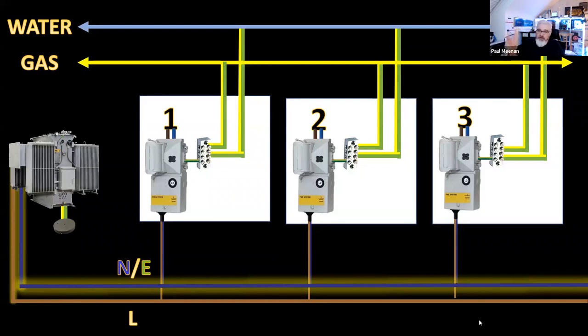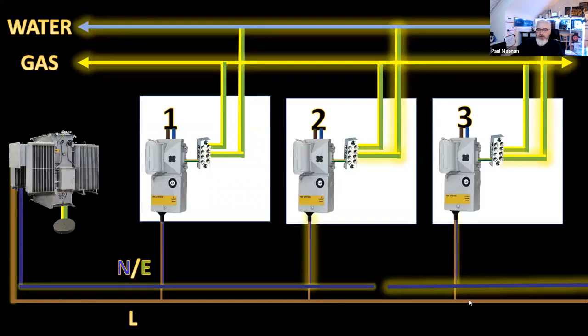But if you have a broken PEN, which Dave is going to magically make happen, very simply what occurs is that joint over time will slowly go high impedance, high impedance, high impedance. When you have a broken PEN within installation 3, you could have 240 volts on all your metalwork. As that PEN breaks down, you get diverted neutral, which may take the path of least resistance, which in this house could be the gas and water main. It will then bypass, so it won't be 4 amps out of house 3 and 4 amps into house 2, you may get 2 amps because it takes the path of least resistance. That's the whole phenomenon of diversion.